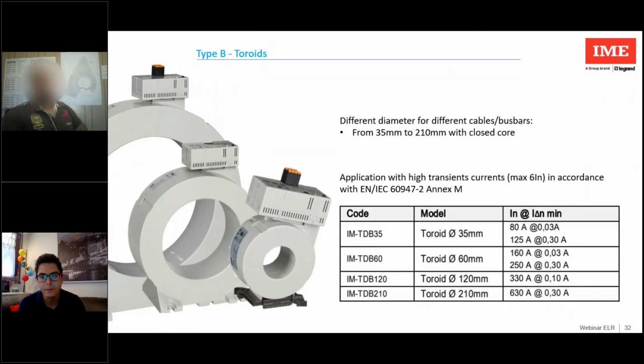These toroids are different from the classic type A or type AC. As I said, type B must be able to read both alternating and direct current. For this, inside the toroid, we find 2 cores and 2 windings, precisely one for the continuous component and the other for the alternating. Here too, we find different holes or windows and different diameters to pass the cable or the busbar. Based on the hole chosen and the nominal current of the system, there will be a minimum differential current that can be detected and set on the relay, like the AC.